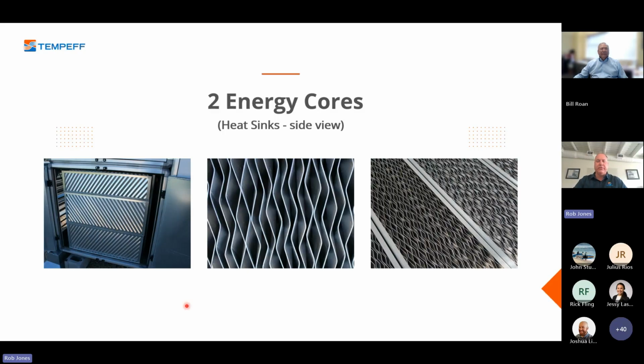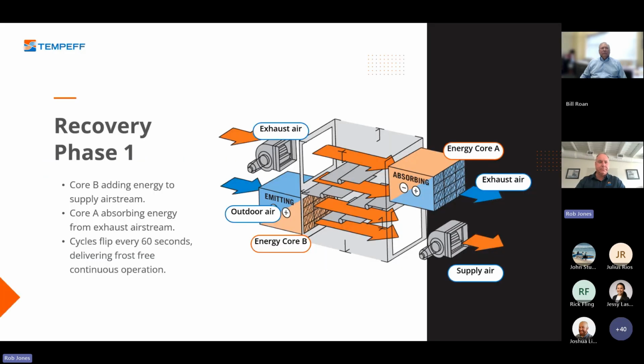It's 60 pounds. That's a service person with work gloves. Not hundreds of pounds like heat wheels can be. Corrugated aluminum, and we take every second sheet and we flip it. It creates a very haphazard or random pattern. This is for 2 purposes. 1, larger air flutes, so dirt and debris do not become a factor. And 2, this causes air turbulence. And when the air is tumbling through our heat exchangers, it makes it easier for the aluminum to scrub out and retain that energy. It has 2 recovery phases.